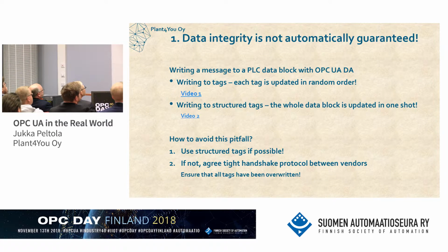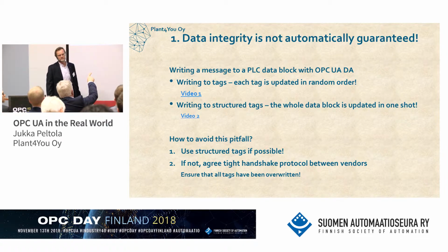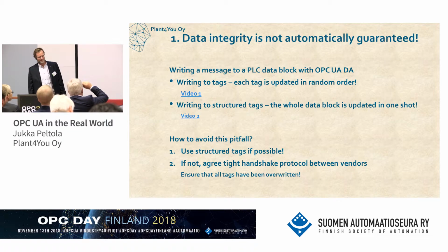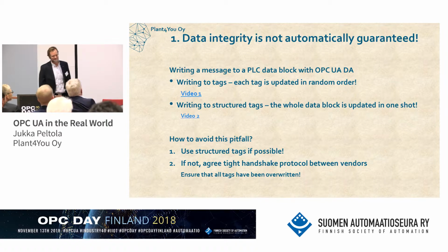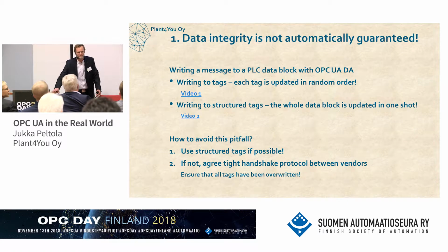If we take another example, when the another client was able to, yes? Did you expect that it's not written in random order? No. It's not ensured by OPC UA? No, no. It's not. In the companion specs, that's what we typically use methods to do. But that's why we didn't have any methods on servers.